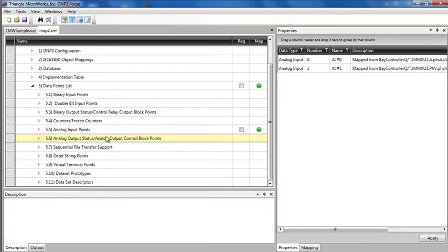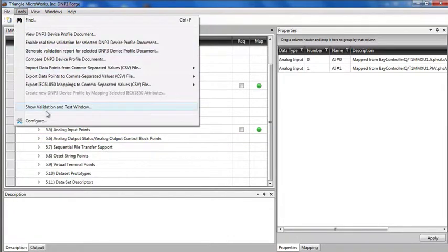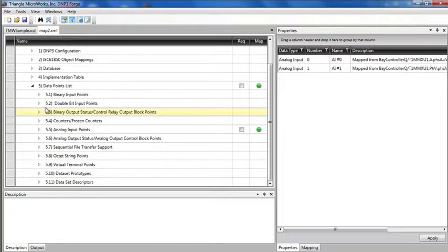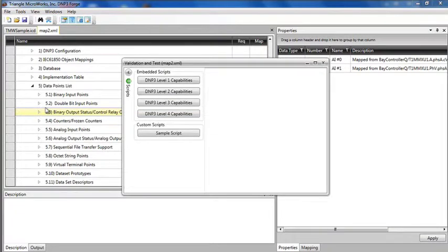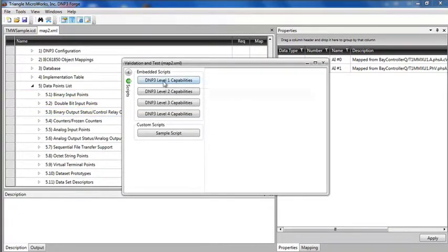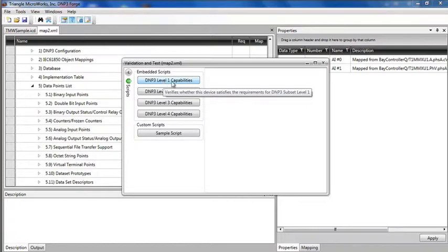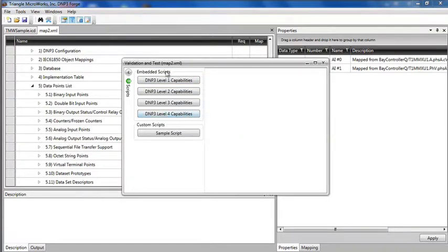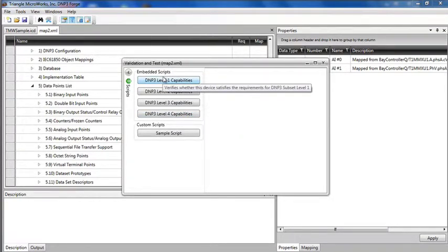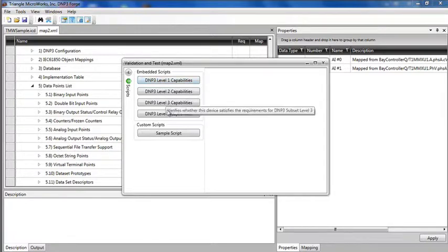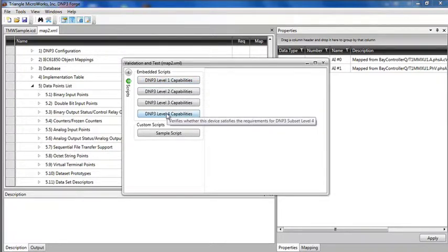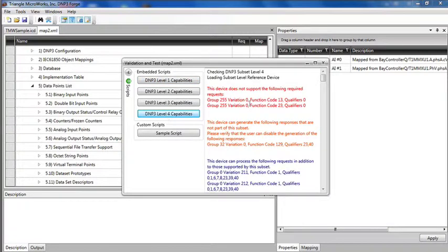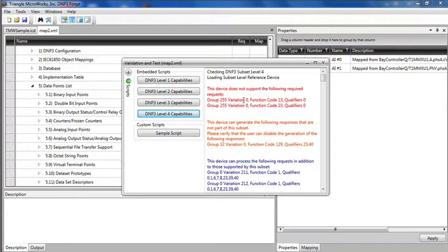I'll move on to show some additional features of DNP3 Forge. I'm going to go to the tools menu and select the validation and test window. This window demonstrates scripting capability of DNP3 Forge. DNP3 Forge allows you to customize it using Python scripts and includes some predefined scripts to do DNP3 level capability validation. For example, if I want to take the device profile I just created and validate it against level 4.